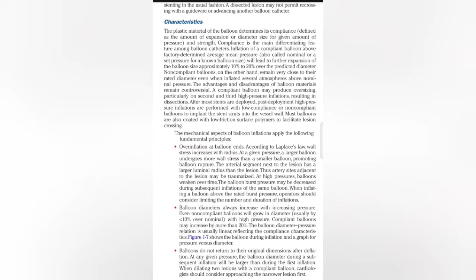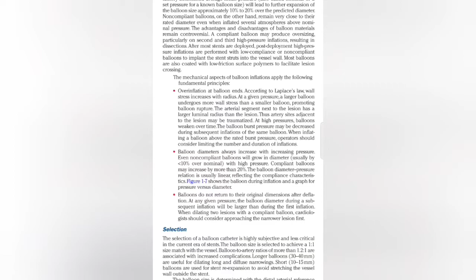Even non-compliant (NC) balloons will grow in diameter, usually by nearly 10% over nominal with high pressures. Compliant balloons may increase by more than 20%. The balloon diameter-pressure relation is usually linear, reflecting the compliance characteristics. Balloons do not return to their original dimensions after deflation. At any given pressure, the balloon diameter during a subsequent inflation will be larger than during the first inflation. When dilating two lesions with a compliant balloon, cardiologists should consider approaching the narrower lesion first.